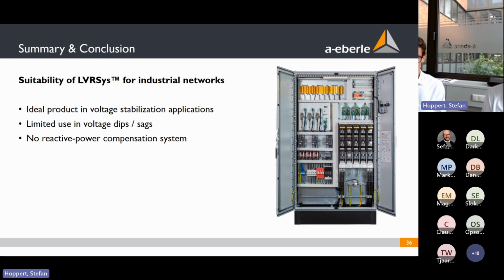And the cost comparison to a controllable transformer: we expect we are more or less the same, but we have another advantage. We can balance the three-phase system. That's not possible with a normal controllable transformer. And the controllable transformer also needs a lot of maintenance. If the voltage fluctuation on the secondary side is high, especially in some applications in the HVDC area where the voltage fluctuation for the self-consumption is really high, the system runs very often and steps up and down very often. That means it's a lifetime issue, and we have a lot of advantages compared to a controllable distribution transformer at this time.